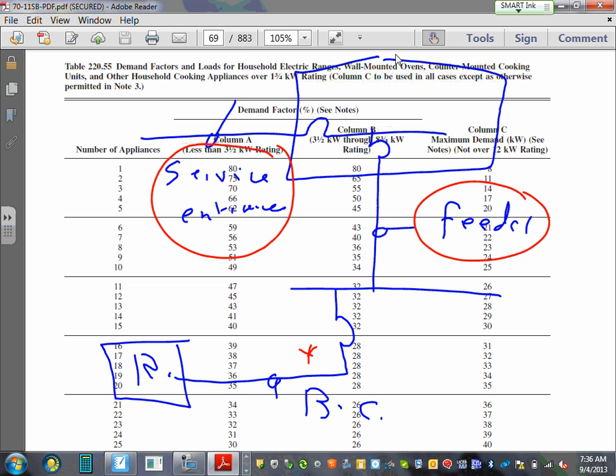If you have an apartment building, let's just say a 10-story building, each story is an apartment. What's the likelihood that each and every one of them will be using his or her electrical range simultaneously, fully loaded? Not likely, right? So those smarter than you and I decided to have this table so they can derate. Meaning they take the sizes of the ranges in this apartment building and they cut it. Who cares? When you cut it, you reduce the size of the service that's coming to your building. You basically reduce this size here. When you reduce the size of the service, as well as the feeders, then the equipment will be smaller, more realistic, cheaper, easy to install.